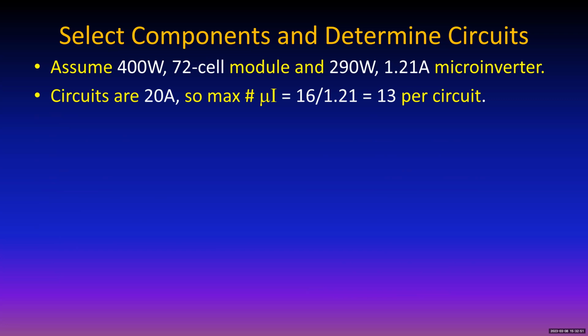So now, it turns out these things go into a combiner box, because if you have maybe 4 or 5 different circuits, you want to combine them down into one, like you do in a distribution panel. In a distribution panel you have fat wires bringing a lot of power in, and then it goes out on the small wires. Here, the power comes in on the small wires and it goes out on the fat wires. It works just the opposite of the distribution panel, and it's called a combiner panel, but it's the same geometry, same everything, pretty much.